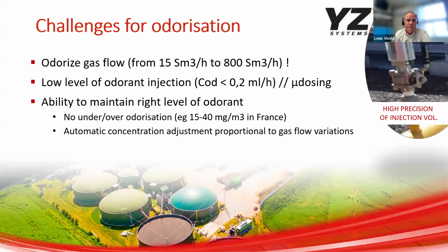Regarding challenges, the major one is a super low gas flow. This is very characteristic of biomethane. Biomethane flow rates can be very low. When I say very low, it ranges from 15 to 800 cubic meters per hour, making odorization a delicate process. So specialized pumps are required to inject precise and tiny amounts of odorants. This is equivalent to injecting a volume of odorant as small as 0.2 milliliter per hour, like a drop, in fact. So maintaining a target odorant concentration is a real challenge. The odorizer system must precisely control the odorant injection and maintain a consistent concentration within a specified range. Under odorization can lead to undetected leaks and generate production shutdown, which will be critical, while over odorization can generate unpleasant odors or high additive cost. So it's very challenging to have an accurate injection. Next slide, please.